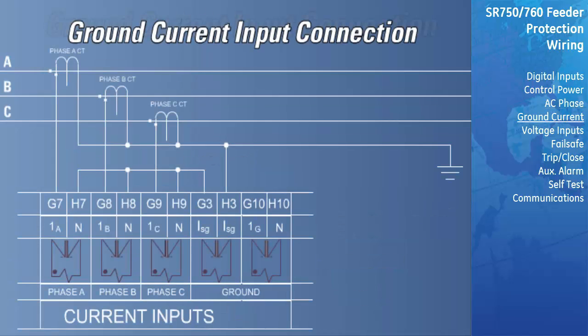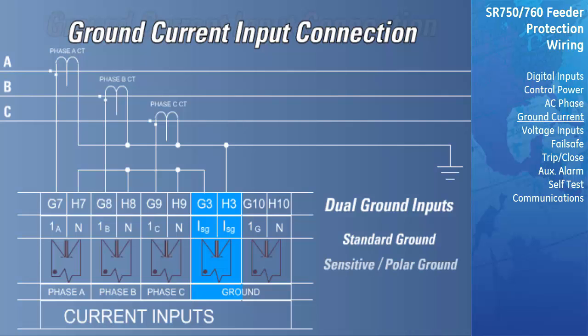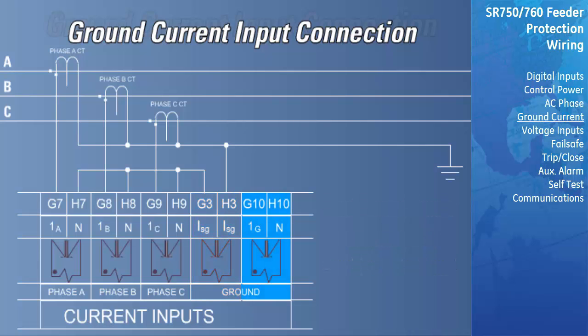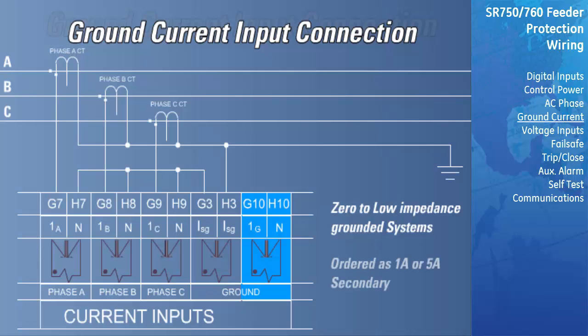Ground current input connection options. There are 2 independent ground CT connections on this relay. Terminals G10 and H10 are the ground connection. Terminals G3 and H3 can be ordered as a polarizing ground input or as a sensitive ground input. The G10-H10 ground connection is intended for low or zero impedance ground systems. The secondary CT value must be specified as 1 amp or 5 amp when the relay is ordered.